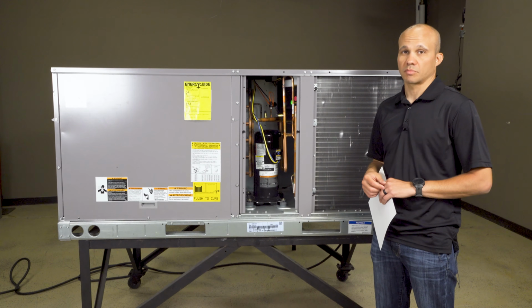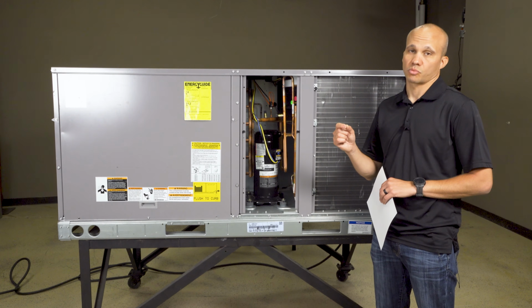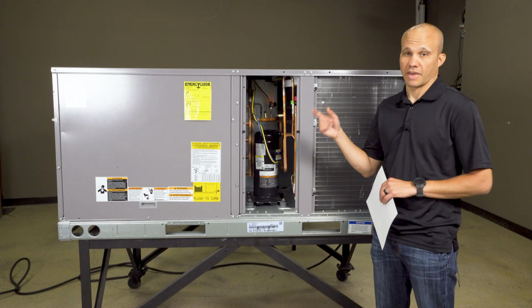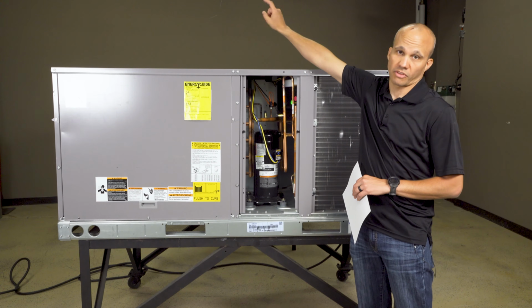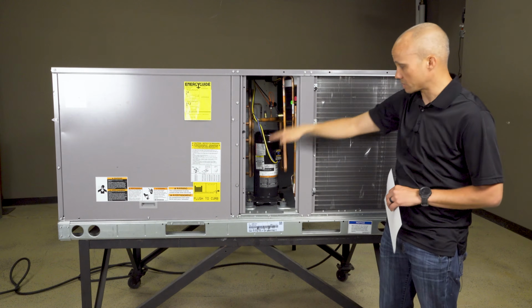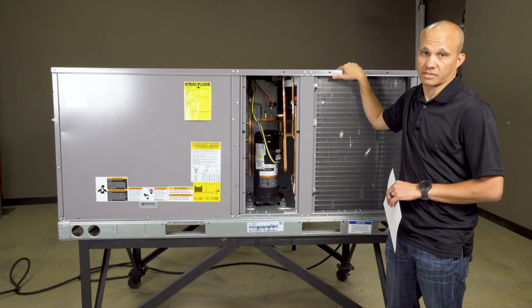What that means in the thermostat is two little switches close. One is for cooling, which is Y and R. The other one is for the fan, which is G and R. So the fan and the cooling turn on together. The fan means the indoor fan that we were talking about before, the evaporator fan. And the cooling means the compressor and the condenser fan will turn on. So all three of those guys will turn on at the same time.